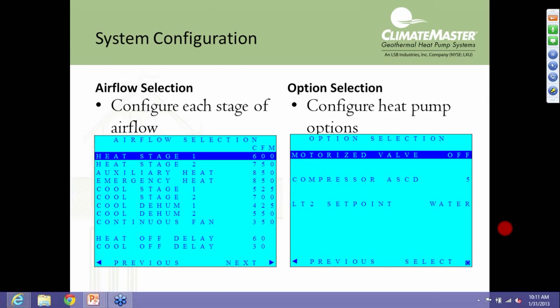The next option beneath airflow is option selection. And under there, there's an item called motorized valve. This is not, and I emphasize not, to be confused with the modulating valve that's inside the heat pump. This is if you want to, for whatever reason or your application, install an external valve, and we're looking for the end switch from that slow opening valve coming back to the board.